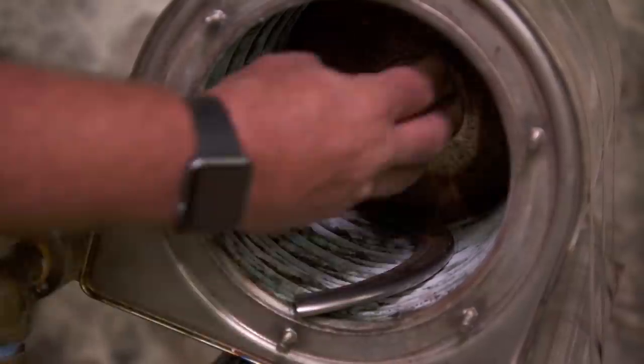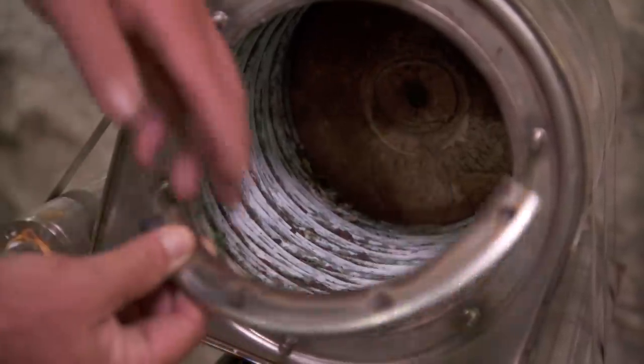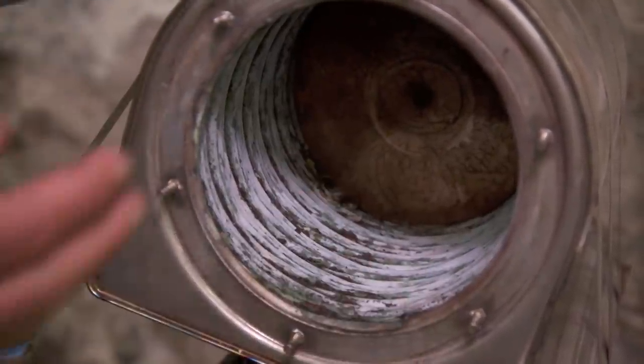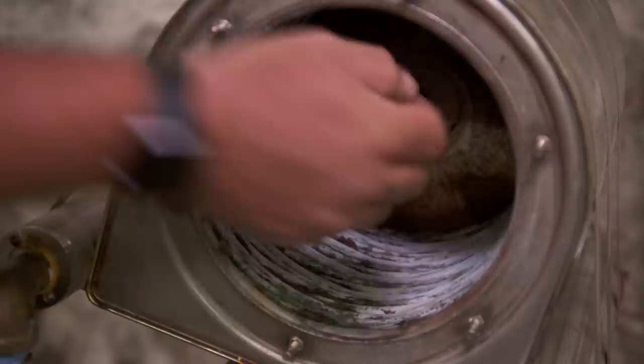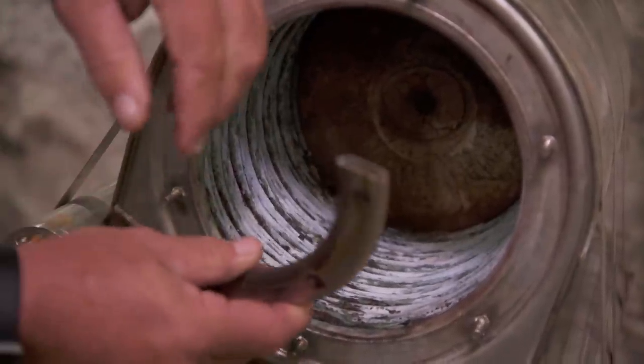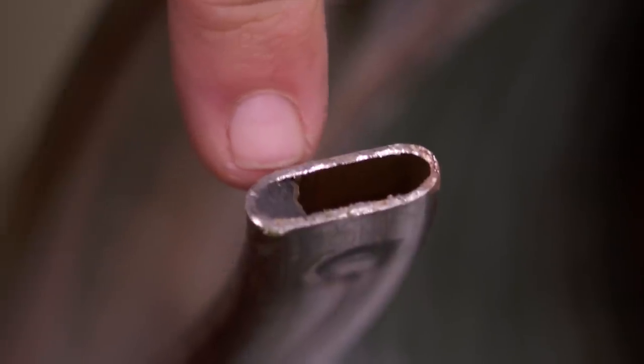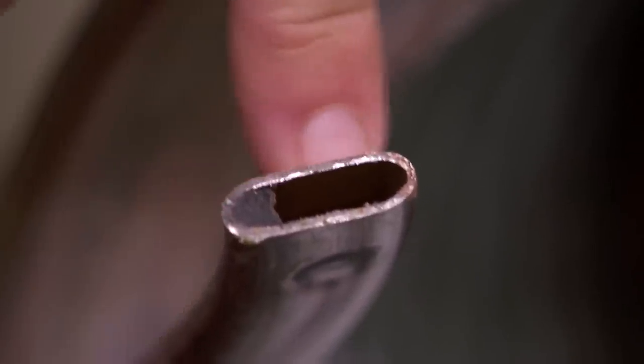Here's a heat exchanger from a typical wall-hung boiler. The burner sits right here, and this is the heat exchanger where water goes through it — it spirals around and water passes through it. The burner tries to drive through and exhaust to the back. What can happen is it can clog in a couple of different places. Right here on the water side, you can see the sludge, and that'll affect heat transfer over time and clog it.